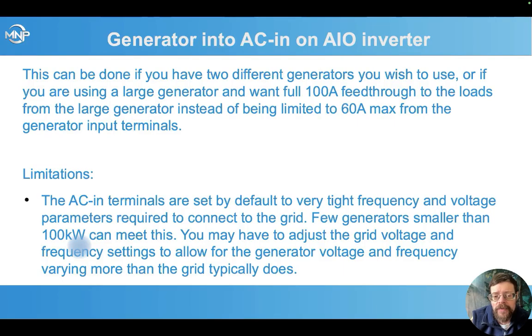So the AC in terminals are default to very, very tight frequency and voltage parameters, and that's because that's what's required to connect to the grid. A lot of generators don't meet that tight of control requirements. Most of them smaller than 100 kilowatts or even 500 or 600 kilowatts can't meet those requirements. So you're going to have to go in and adjust all the grid voltage and frequency settings, which are now basically adjusting it to let it connect to a generator on those terminals instead of the grid. So those can be opened up a bit to allow it to stay connected to a generator on those terminals.